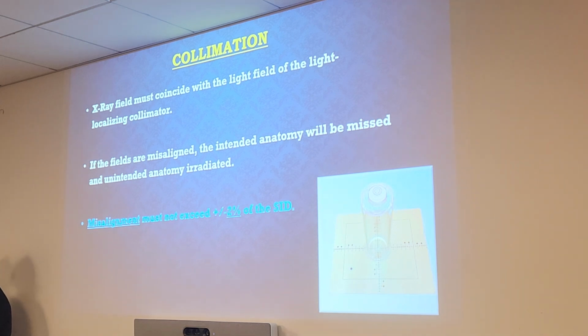So for collimation, the most important thing that you need to remember is the misalignment must not exceed plus or minus 2% of the SID.